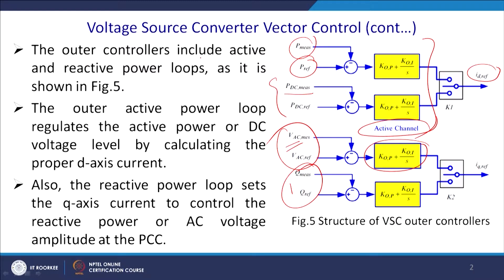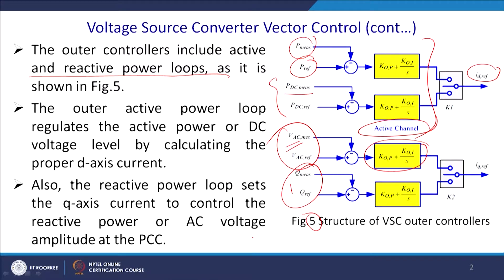The outer control includes an active and a reactive power loop as shown in Figure 5, following the same notations as the previous class. The outer active power loop regulates the active power or the DC voltage level by calculating the proper D-axis (real axis) current using a PI controller. The reactive power loop sets the Q-axis currents to control reactive power and the AC voltage amplitude at the point of common coupling (PCC).